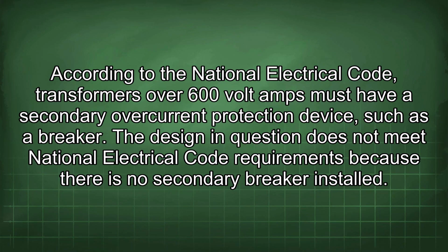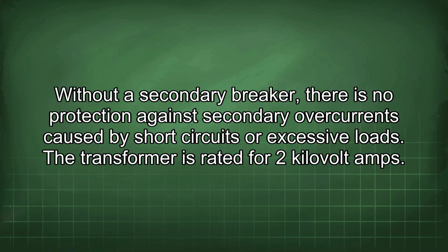According to the National Electrical Code, transformers over 600 volt amps must have a secondary overcurrent protection device, such as a breaker. The design in question does not meet National Electrical Code requirements because there is no secondary breaker installed. Without a secondary breaker, there is no protection against secondary overcurrents caused by short circuits or excessive loads.